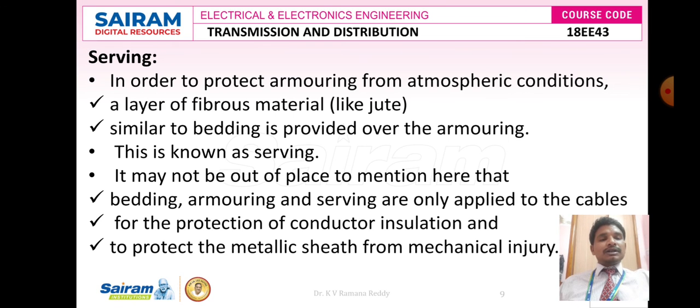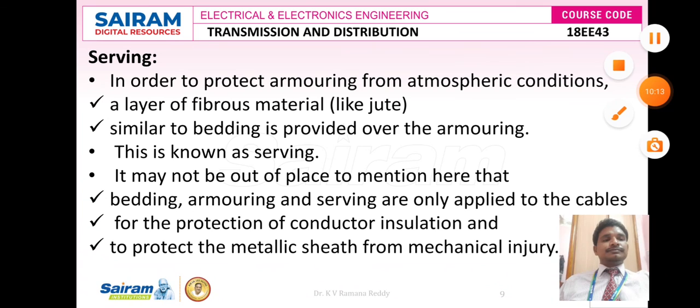Serving is nothing but one fibrous material like jute which is commonly used to protect the galvanized steel wire. This is known as serving. It may not be out of place to mention here that bedding, armoring and serving are only applied to the cables for the protection of conductor insulation and to protect the metallic sheath from mechanical injury. Thank you.